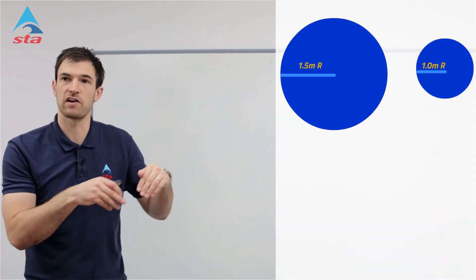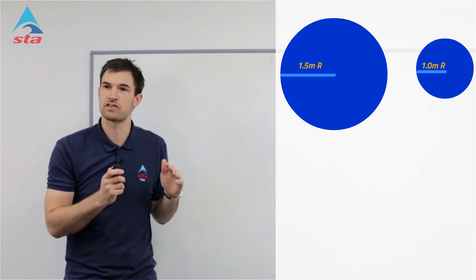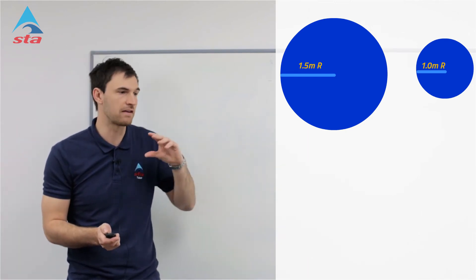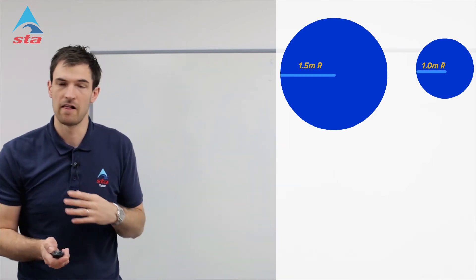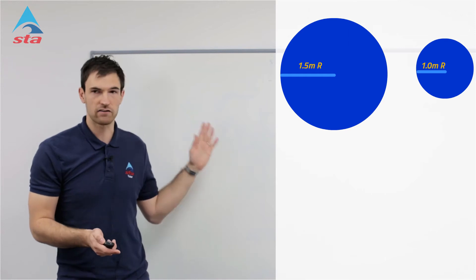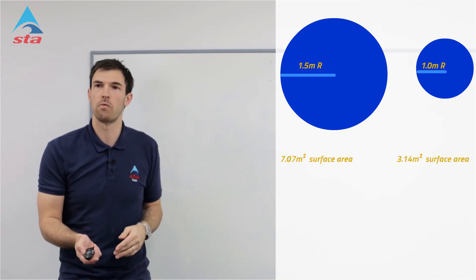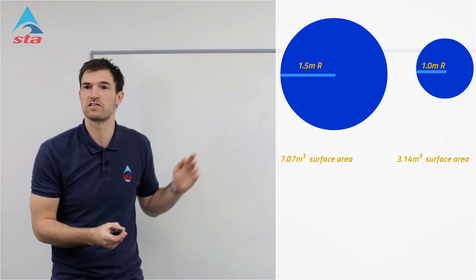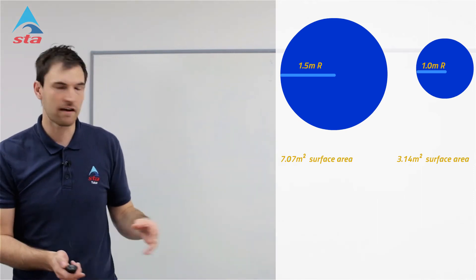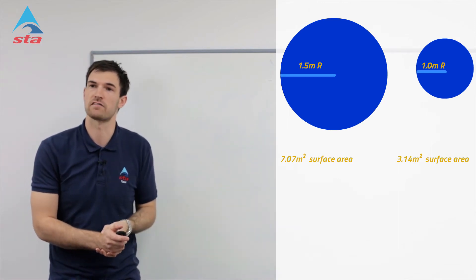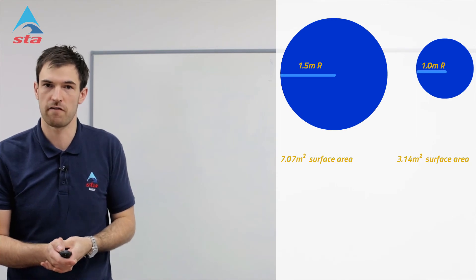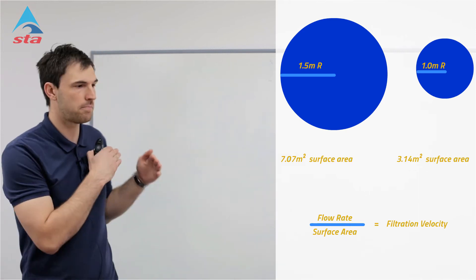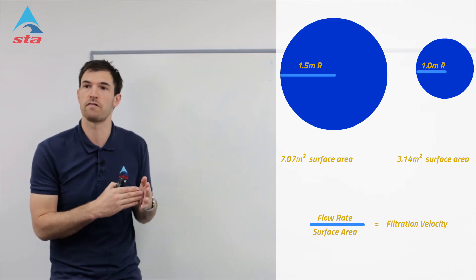If you look downwards on top of your filter it's going to be in a circle shape, and we have to work out the surface area of that filter to start with. On most conventional filters this will be indicated on the side or in the manufacturer's guidance document, but if you want to work it out it's a simple method: area of a circle is π r². We've got two filters here for comparison. Filter one has a 1.5 metre radius: π × 1.5 × 1.5 gives us 7.07 m² surface area. Filter two, slightly smaller, has a 1 metre radius, giving us a 3.14 m² surface area. The flow rate delivered from the circulation pumps divided by the surface area of the filter gives you the filtration velocity — the downward speed through that filter.